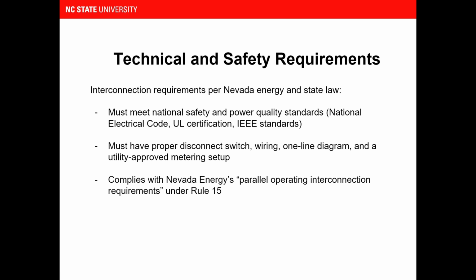Alright, next let's talk about the technical and safety requirements that apply to every interconnection project. Nevada standards rely heavily on nationally recognized electrical and engineering codes, so a system must meet the National Electrical Code, along with the relevant UL certifications, for example, UL 1741 for inverters, and must also follow IEEE standards for power quality, grid interaction, and equipment performance. The system also needs to include a proper disconnect switch, compliant wiring, and a detailed one-line electrical diagram showing exactly how the system connects to the property and the grid. NV Energy will also evaluate the customer's metering setup to make sure that it supports the net metering or export measurement.